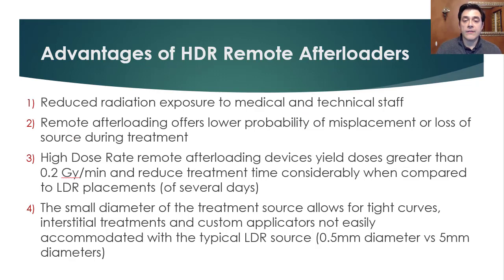The advantages of having an HDR remote afterloader, well, the first one being that there is reduced radiation exposure to the medical and technical staff. So in the case of the Fletcher suite that was described above, it was a manual afterloader. That means after the applicator was placed inside the patient, then somebody would manually put those sources inside of the patient's applicator, including whatever spacers or whatever geometry concerns needed to have happen. So there is an increase in the radiation exposure to the medical and technical staff that come from having one of these low dose rate or medium dose rate brachytherapy procedures.